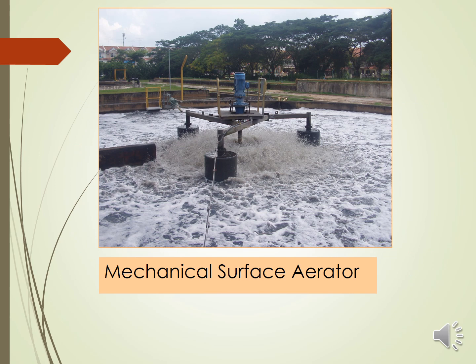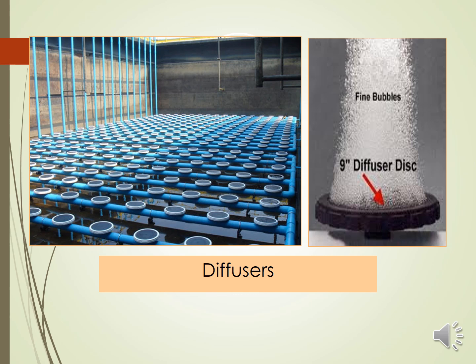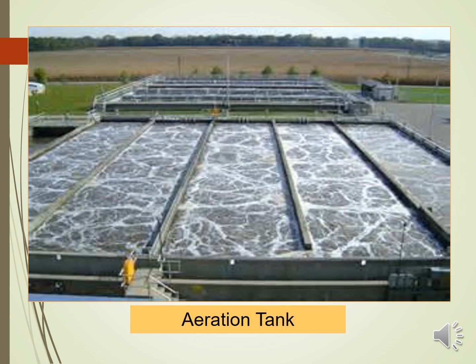This photo shows a mechanical surface aerator floating on the surface and mixing the wastewater. This photo shows diffusers placed at the bottom of the tank, producing very fine air bubbles. These fine bubbles increase the contact between air and water, providing more oxygen to the wastewater. This other photo shows the aeration tank from the top.